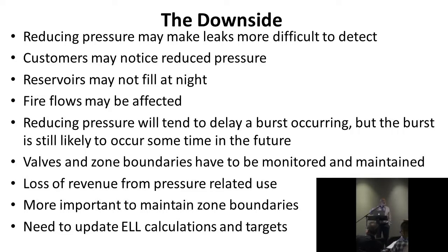Some of your reservoirs may not fill at night, but generally speaking, part of your design will be to make sure you'll get water up to the top end of your highest reservoir. Fire flows may be affected, so you may have difficult discussions with your fire services, fire authorities. I had very many difficult discussions with my fire authorities, to the extent that at one stage we were up to then referring them to being pressure reduction schemes and pressure reducing valves.